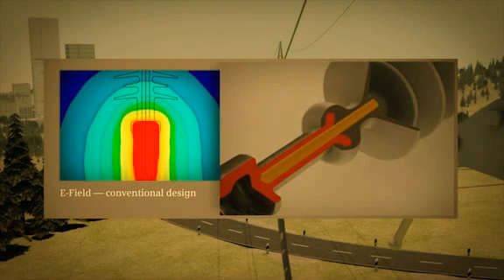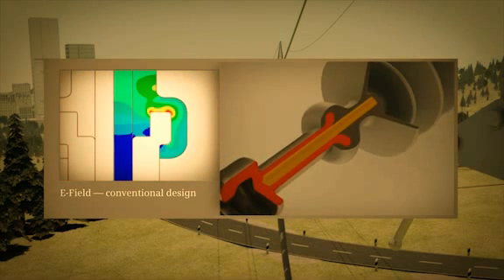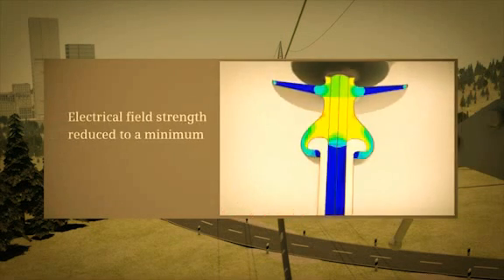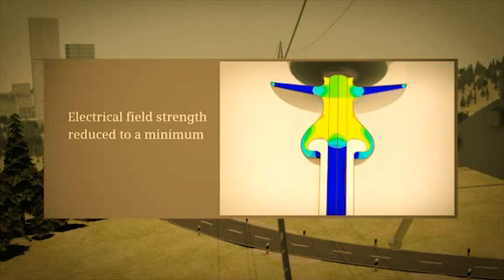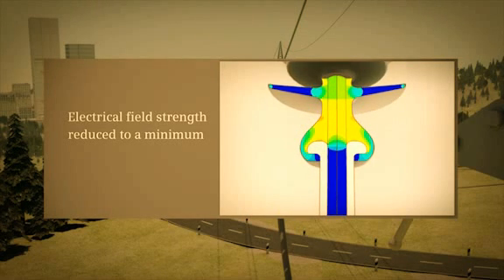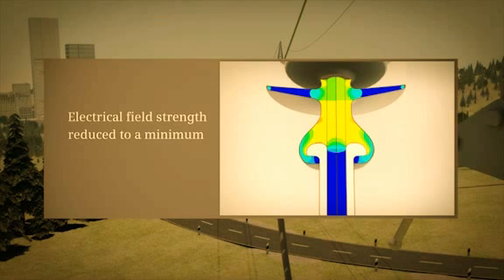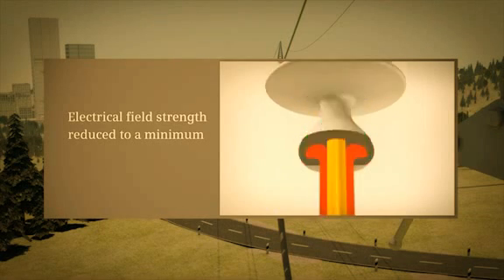Furthermore, electrical field strength and partial discharge inside the junction zone, as well as on the silicone housing surface, have been reduced to a minimum by modeling a grading ring. This reliably prevents corrosion of the insulating material and eliminates the risk of subsequent insulator failure.